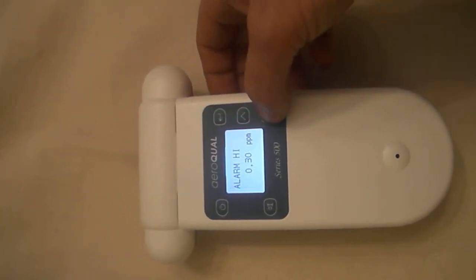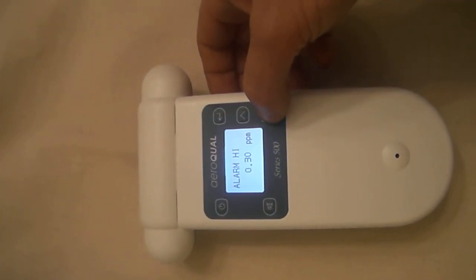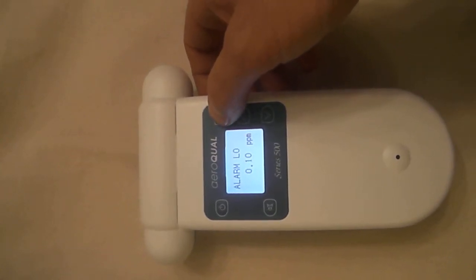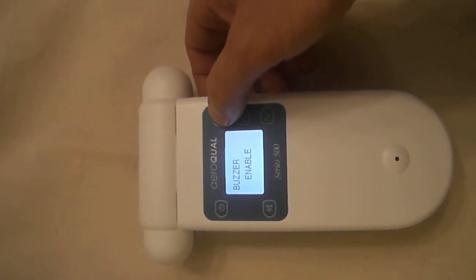We can view what the sensor head is. We can set the alarm points. There is a high alarm point and a low alarm point. We can turn the audible alarm on or off.